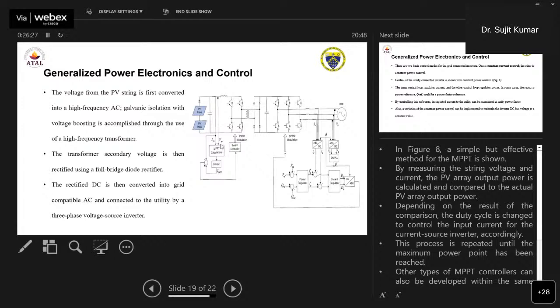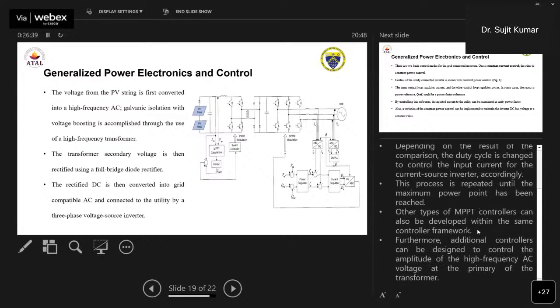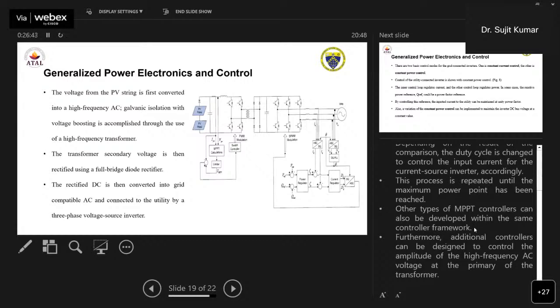So we keep changing the duty cycle based on the power, accordingly, when we are controlling the input current. Other types of MPPT controllers can also be developed within the same controllers. Additional controllers can also be designed to control the amplitude of the high frequency AC voltage at the primary of these transformers. So with these additional controllers, you can vary the duty cycle in such a way that it reaches the maximum power point even with lesser power.